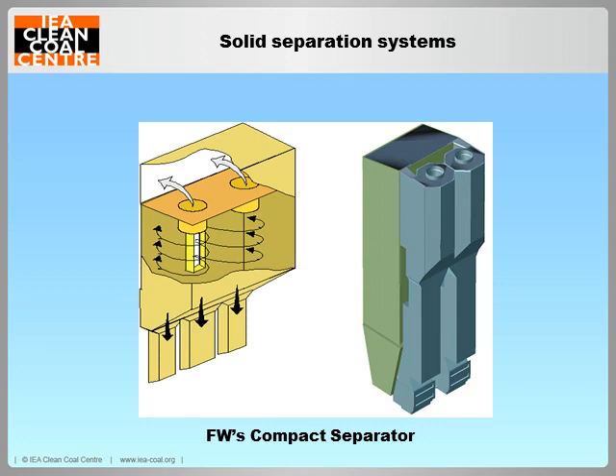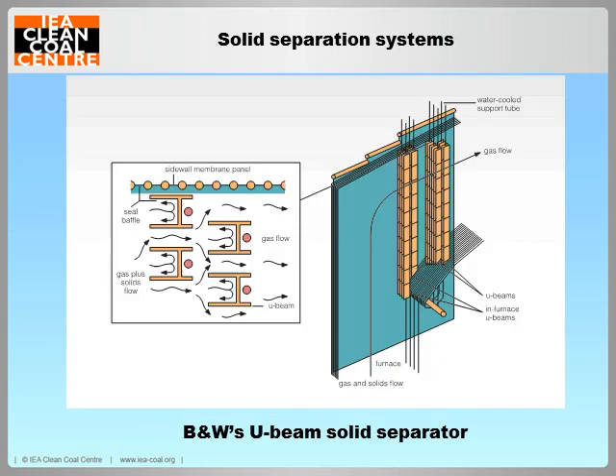This figure shows the compact separator design introduced by Foster Wheeler, which uses pentagonal-shaped membrane water walls with a thin layer of refractory inside the separator to smooth out the corners, and has a smaller footprint. For smaller CFBC boilers, impact separators such as the Babcock & Wilcox two-stage solid separation system are used. Several other cyclones with novel designs are under development at the moment.